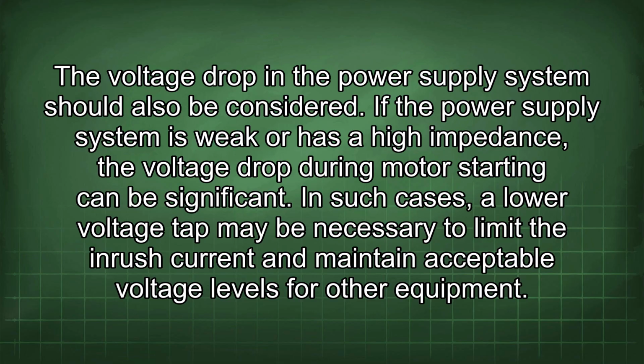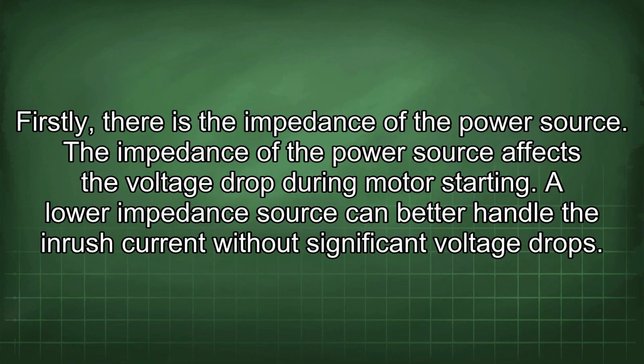If the power supply system is weak or has a high impedance, the voltage drop during motor starting can be significant. In such cases, a lower voltage tap may be necessary to limit the inrush current and maintain acceptable voltage levels for other equipment. Firstly, there is the impedance of the power source. The impedance of the power source affects the voltage drop during motor starting. A lower impedance source can better handle the inrush current without significant voltage drops.